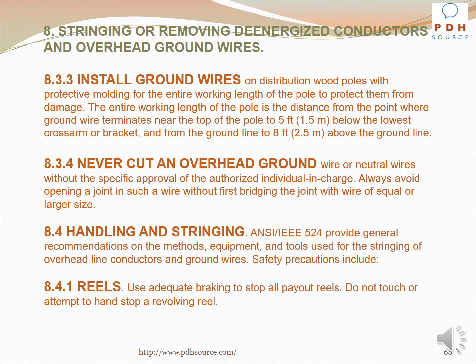Install ground wires on distribution wood poles with protective molding for the entire working length of the pole to protect them from damage. The entire working length of the pole is the distance from the point where the ground wire terminates near the top of the pole to 5 feet below the lowest cross arm or bracket, and from the ground to 8 feet above the ground line.